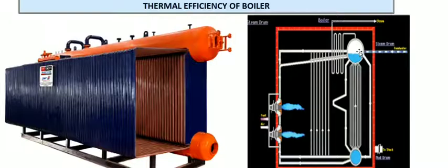Superheated steam can be de-superheated, and then we can convert it into saturated steam. This is also a cross-sectional view of the boiler. So there are the steam drum, mud drum, water wall tubes, downcomers, risers, and fired wall tubes, which we call rear tubes and front tubes. And blowdown will be there in order to maintain the quality of the boiler water. We want to blow down continuously, because due to the continuous heating the water gets concentrated, and the more conductive water we want to blow down by continuous blowdown or intermittent blowdown.